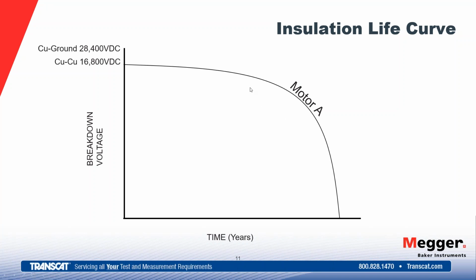And we see as we put it to use, we can expect maybe some certain amount of time that it's doing well, but depending on how we're treating it and what environment that motor's living in, it's going to cause that insulation to degrade over time. And as it starts degrading over time, eventually, when the dielectric strength of that insulation system falls below bus voltage, that's when we have our catastrophic failure, which generally occurs at 2 a.m. on a vacation day, that we end up having that happen to us.